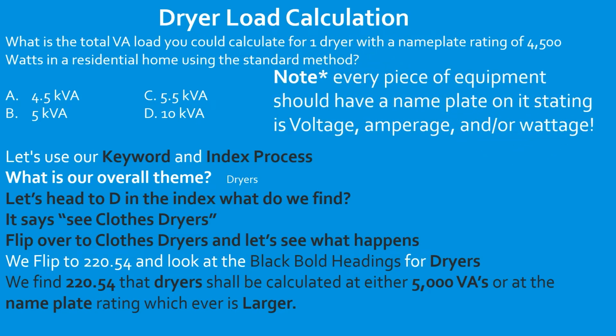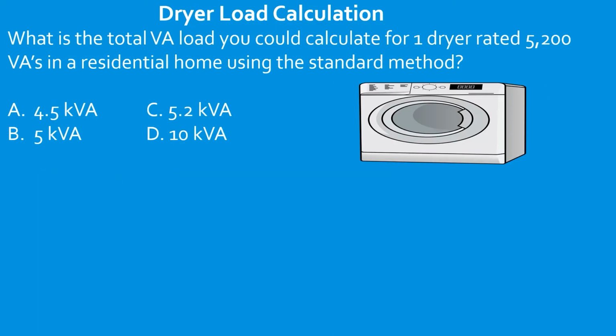I do want to note that every piece of equipment should have a nameplate rating stating its voltage, amperage, and or wattage. But remember, last week we learned how to figure out the wattage, the amperage, or the voltage if we had any of the other two known pieces of the puzzle. So back to answering our original question: what would we calculate for a dryer that had a nameplate rating of 4,500 watts in a residential home using the standard method? We would choose 5,000, because at a minimum it's required to be 5,000 watts. Great job. Let's take a look at another one.